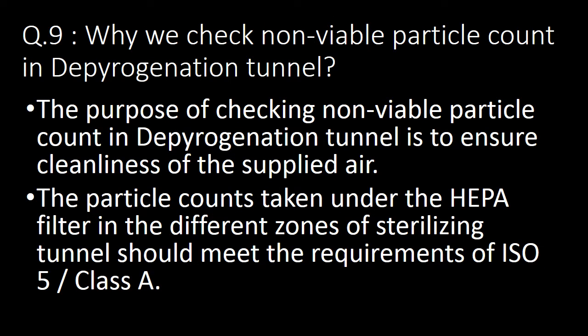Next important question: why do we check non-viable particle count in the depyrogenation tunnel? The purpose of checking non-viable particle count is to ensure cleanliness of the supplied air. The particle counts taken under HEPA filter in the different zones of the sterilizing tunnel should meet the requirements of ISO 5 or Class A.